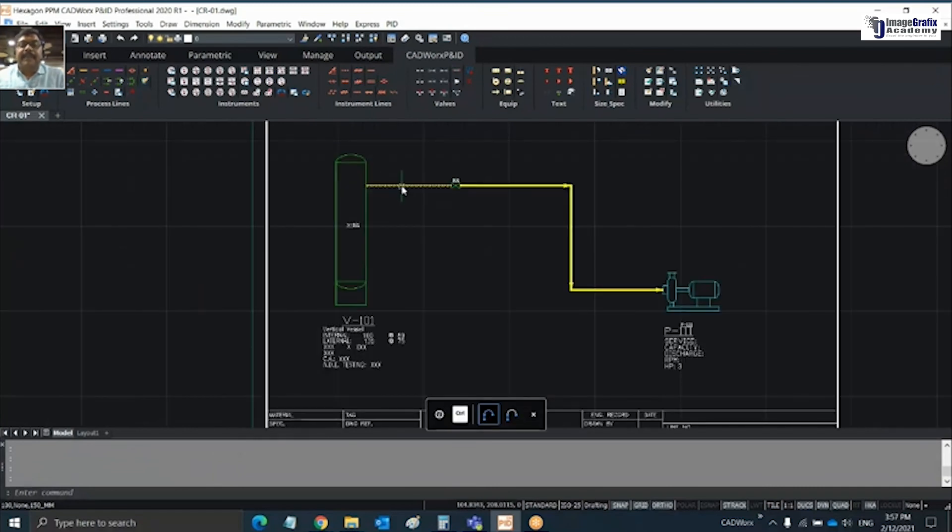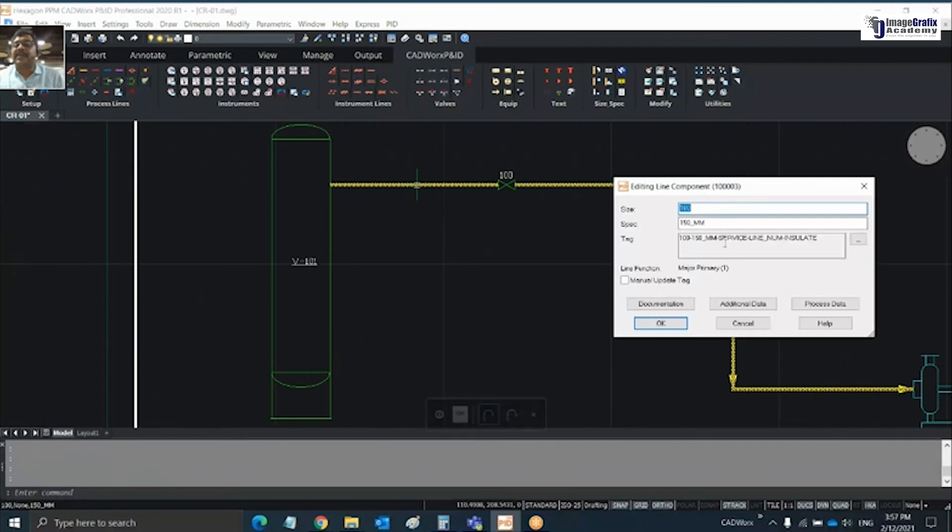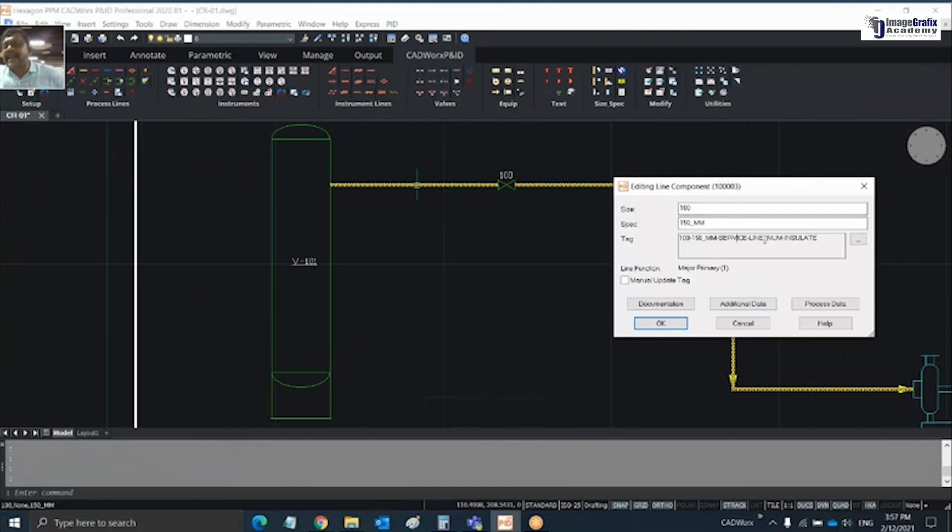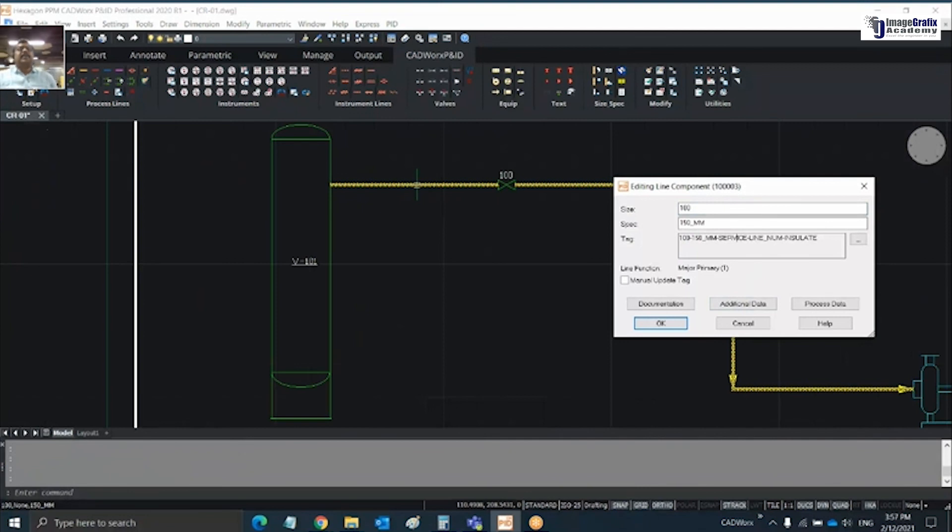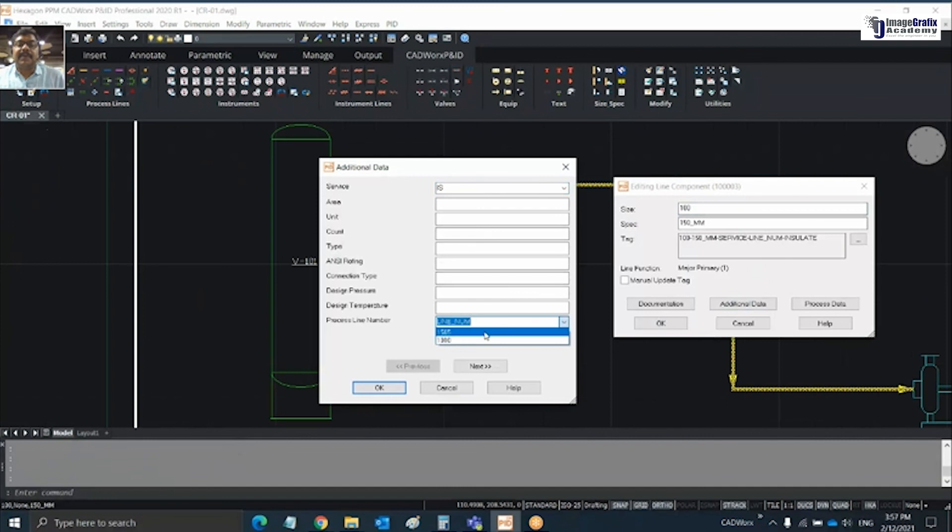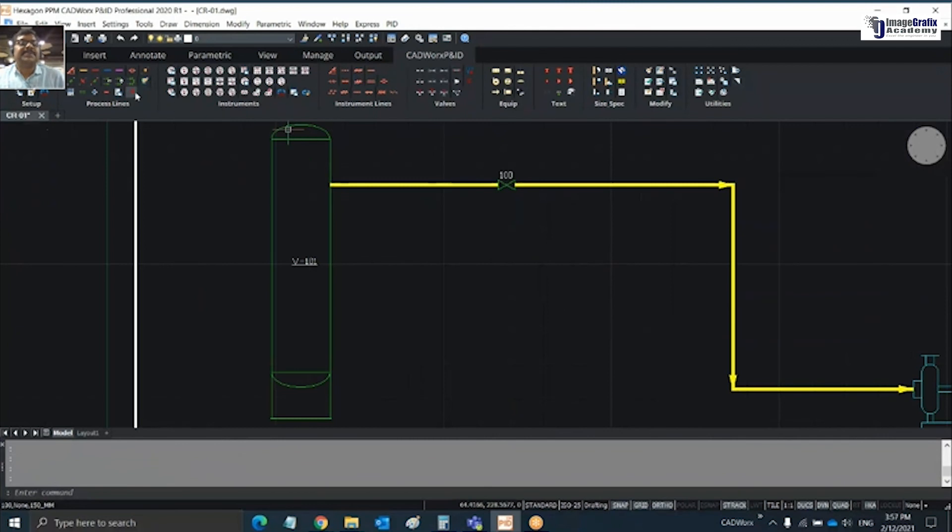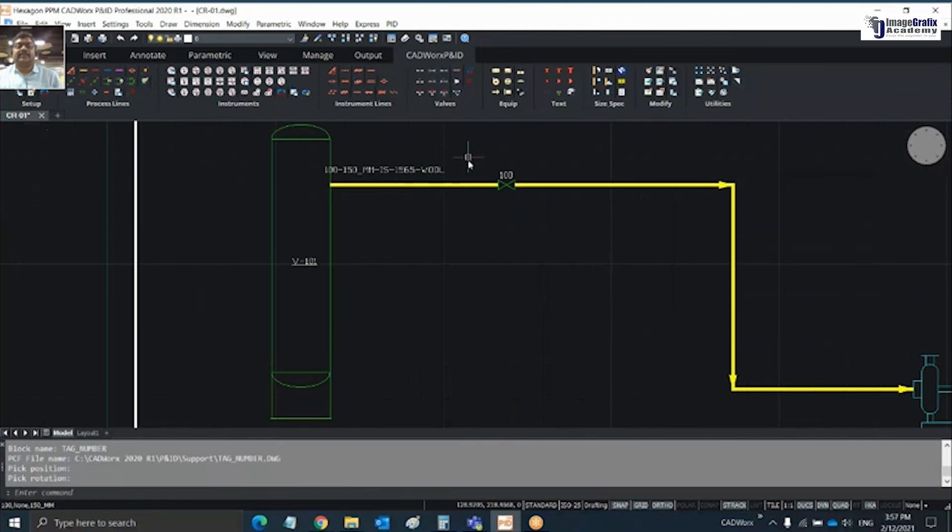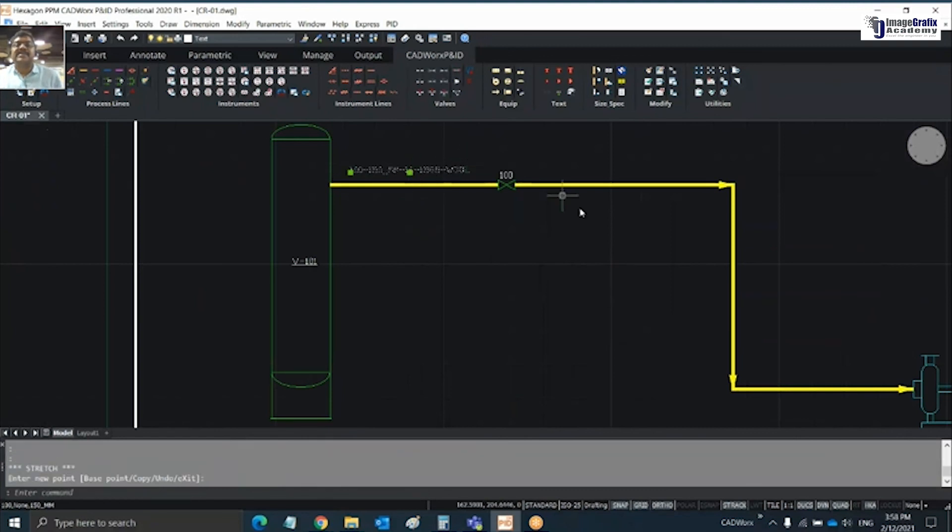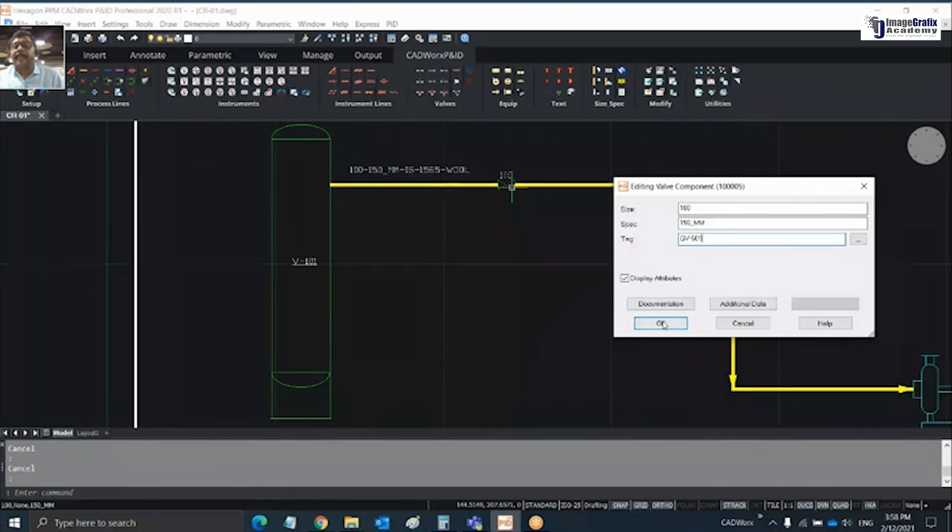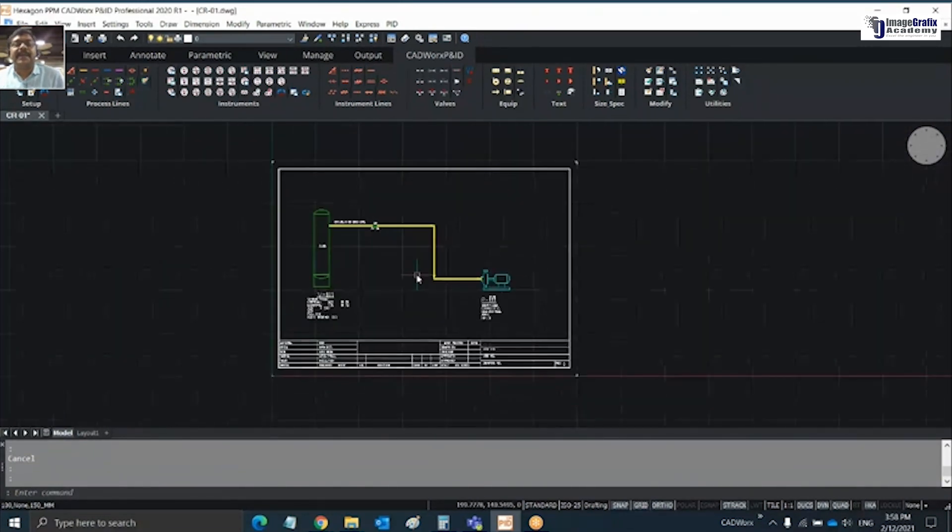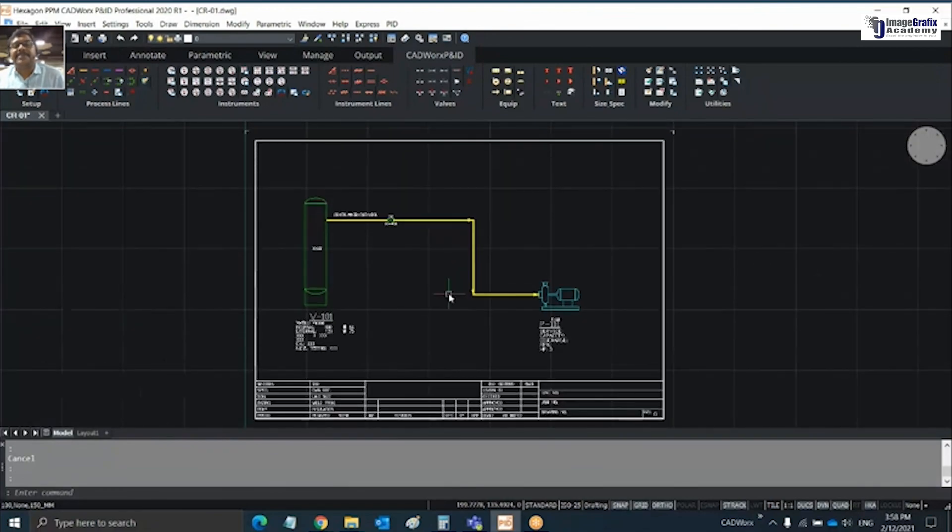Next I would like to define a tag for my process line. Double click on this. It's taking the size and spec, but taking service, line number, and insulation as generic values. Through our drop-down list we defined values, so go for additional data, choose the service, line number, and insulation you want. Click OK. Place the tag here. Similarly for my valve, gate valve as 501. Now my simple P&ID is created and ready.